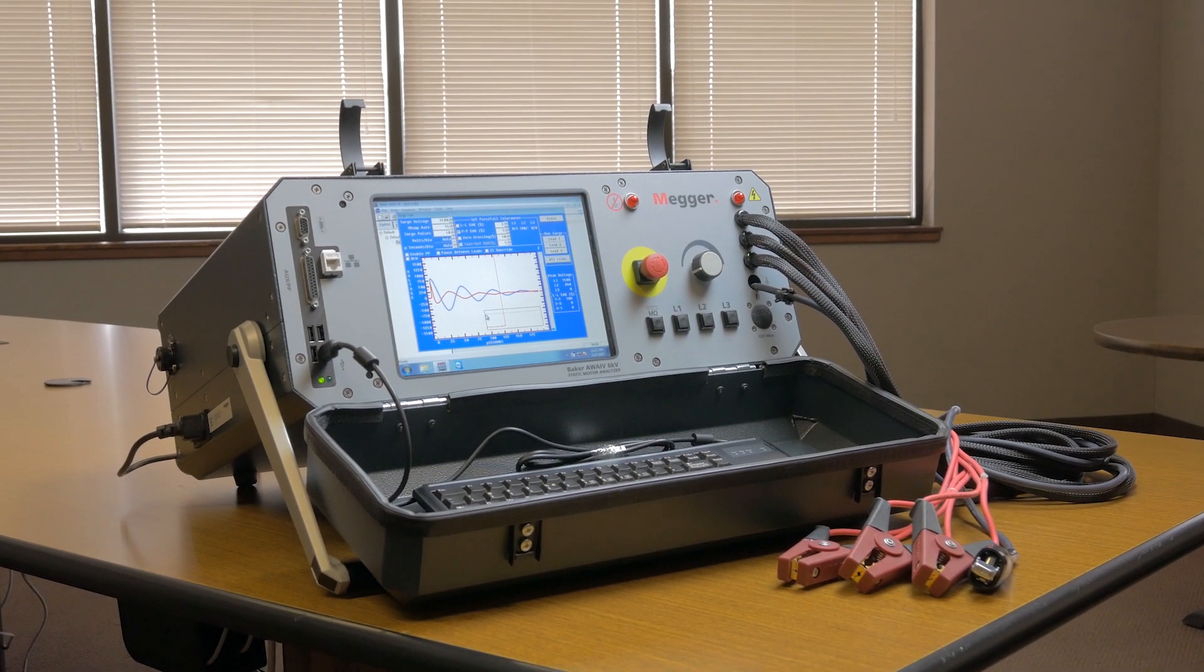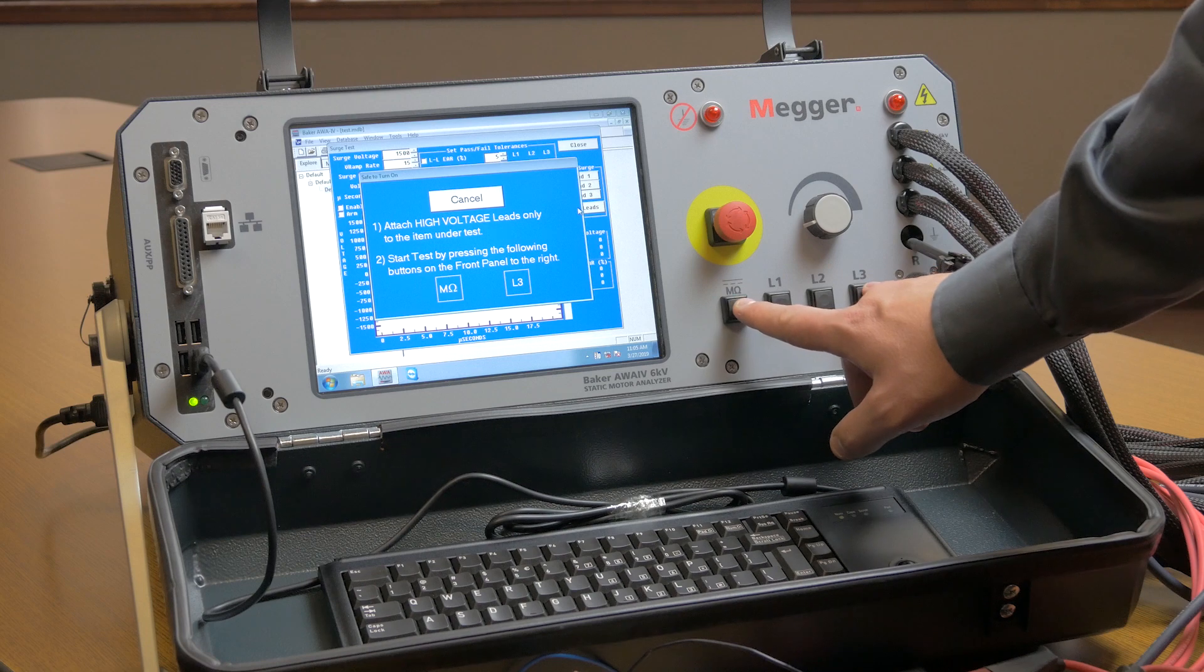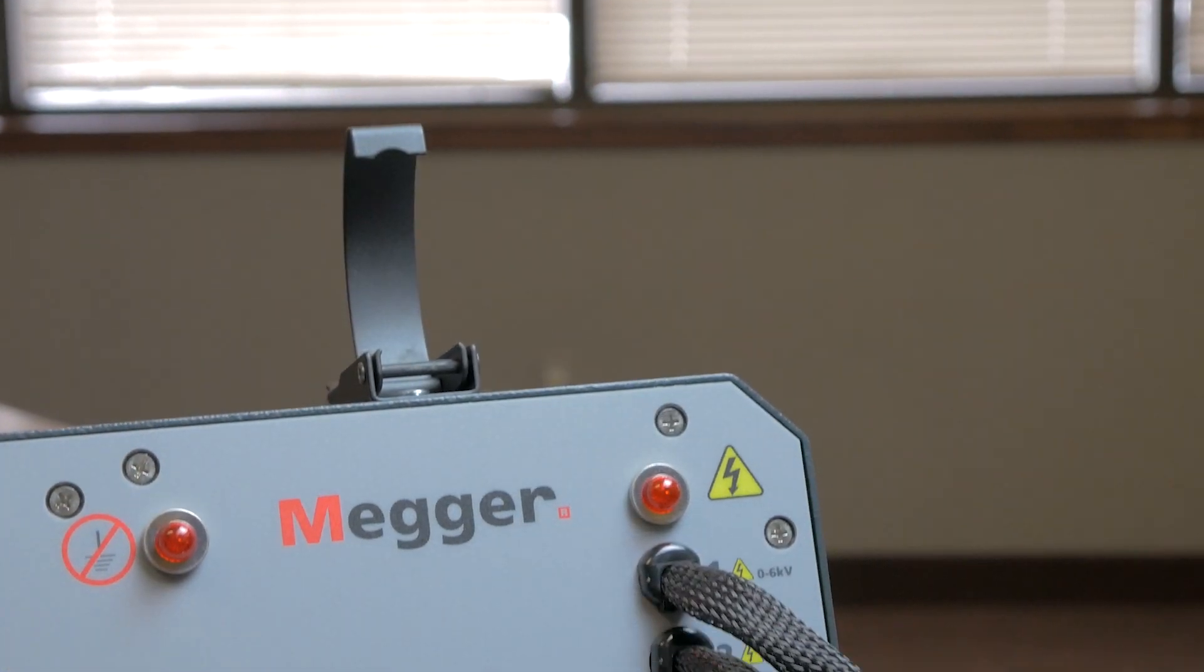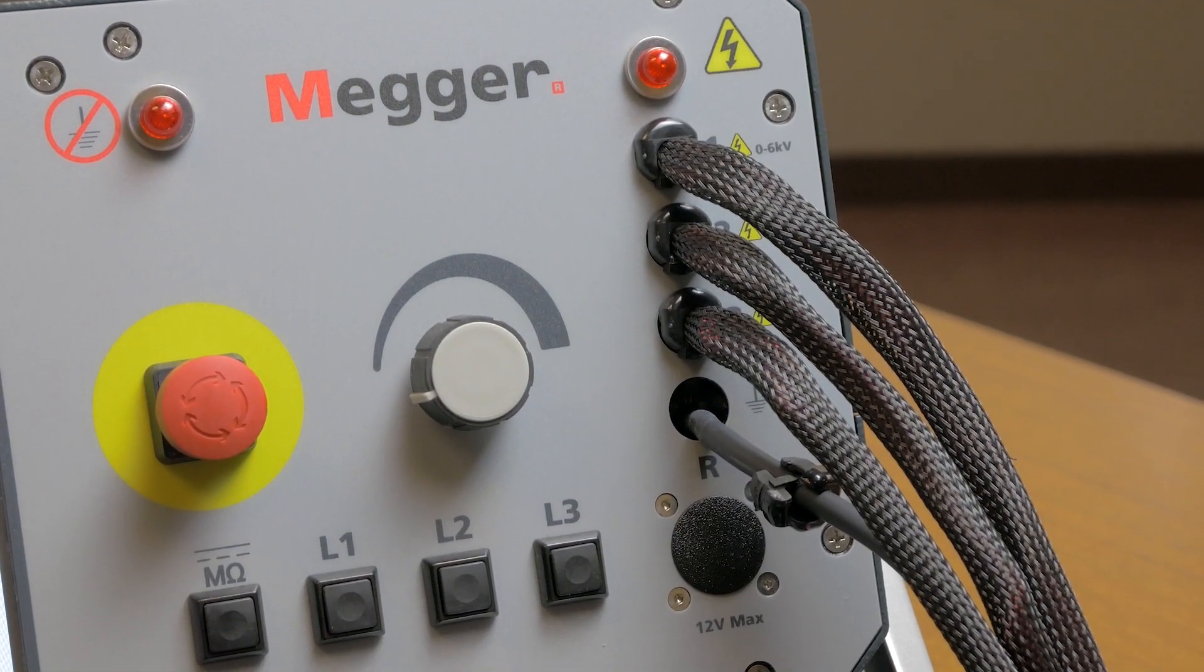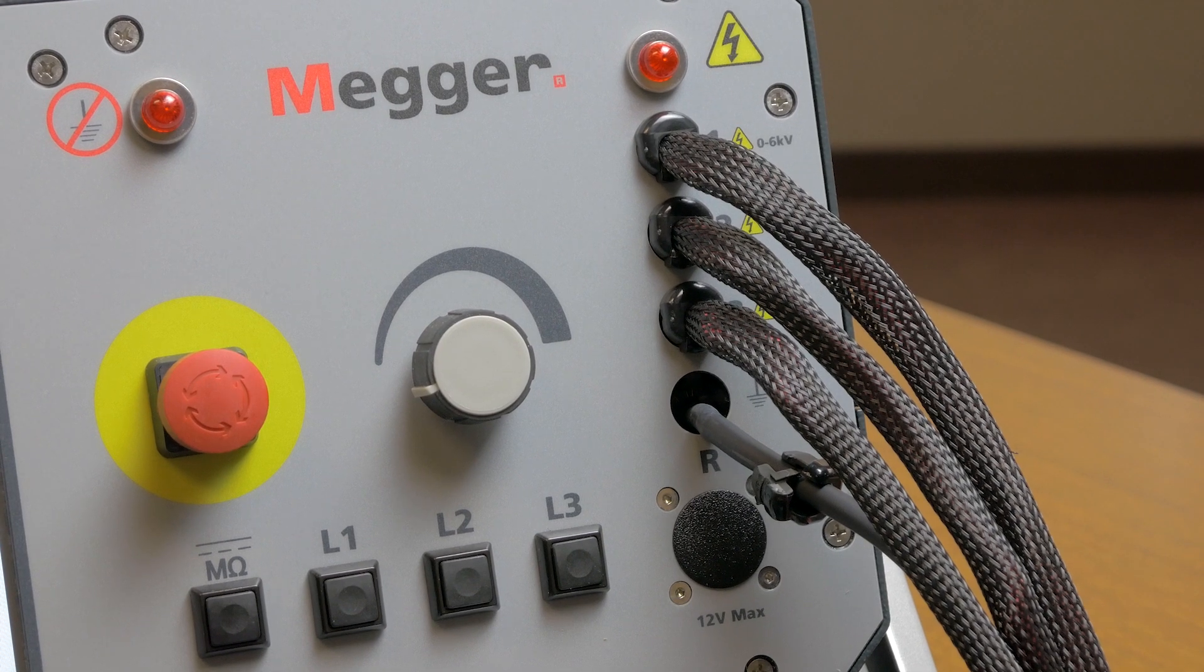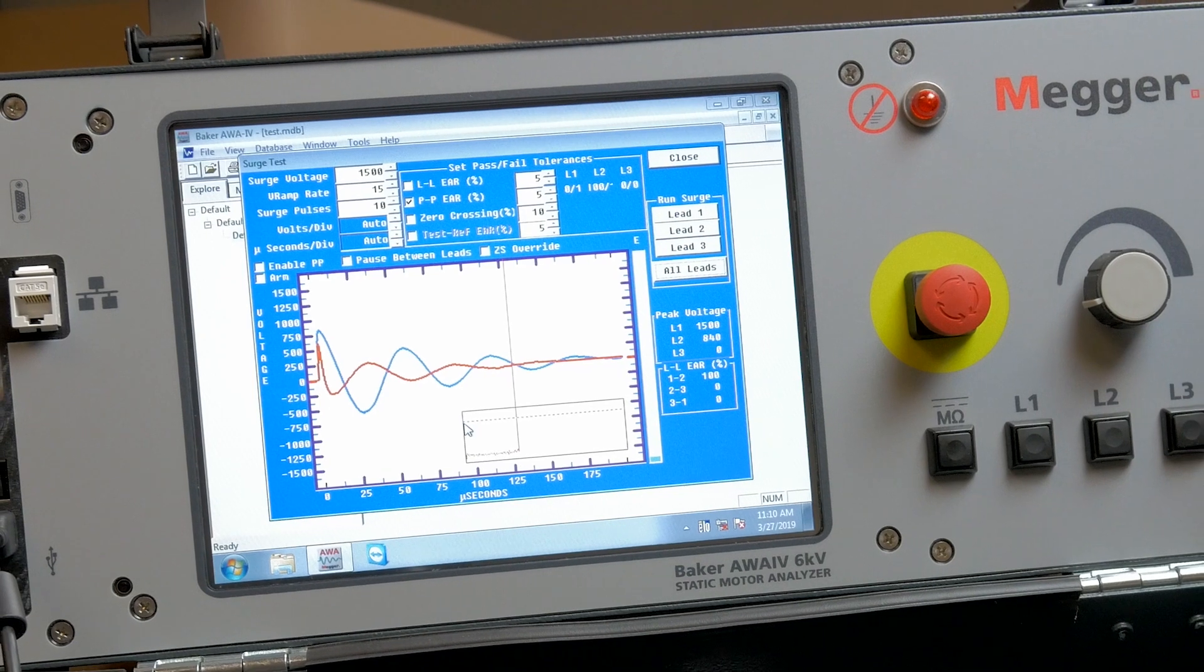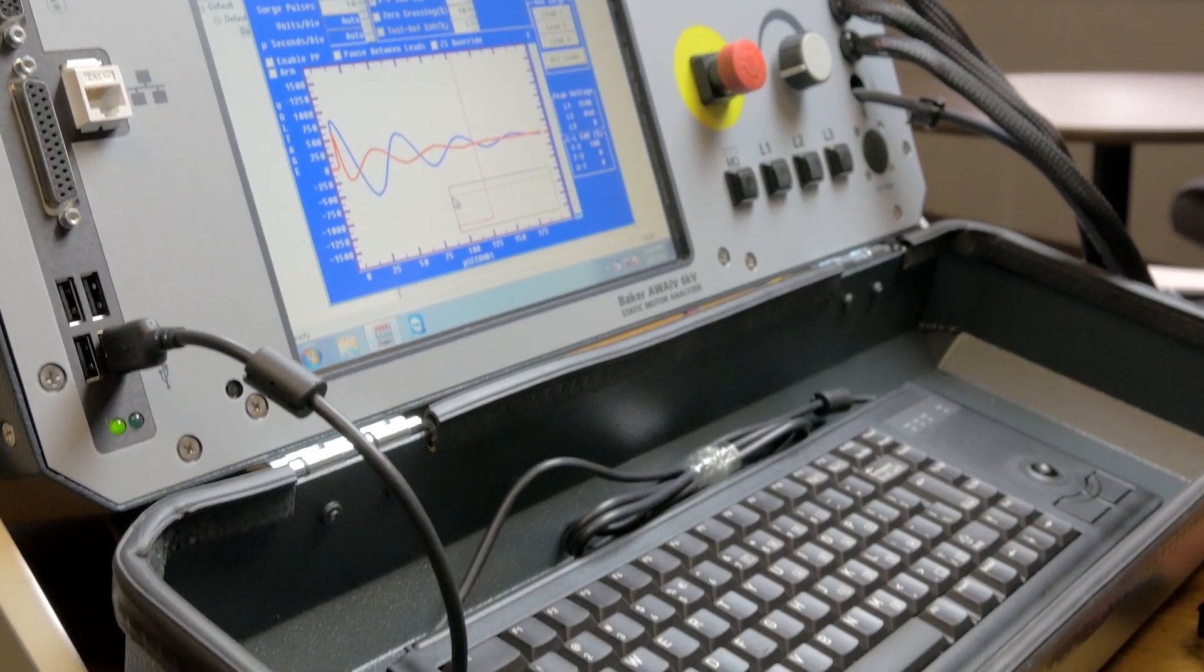The Baker AWA is a fully automated windows-based analyzer with complete insulation testing capabilities. Since it is automated, you can be assured that the testing is consistent and the results are repeatable regardless of who is doing the testing. The AWA has three switched test leads, so all three phases of the motor can be tested without reconnecting the leads. A color touchscreen interface and familiar Windows operating system make this tester easy to use.